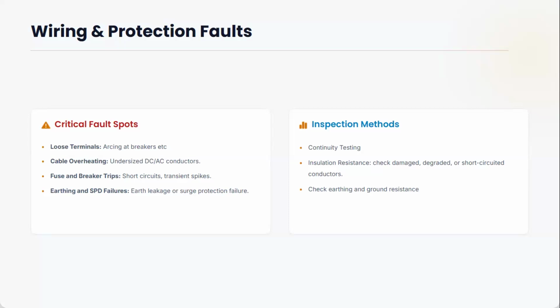Fuses and breakers trip. An overload can quickly trip a breaker. Then this partial contact that we are talking about too: when the breaker rises in temperature due to partial contact, it trips. It won't even get to the rated current before it trips. Then such a breaker will eventually burn out.